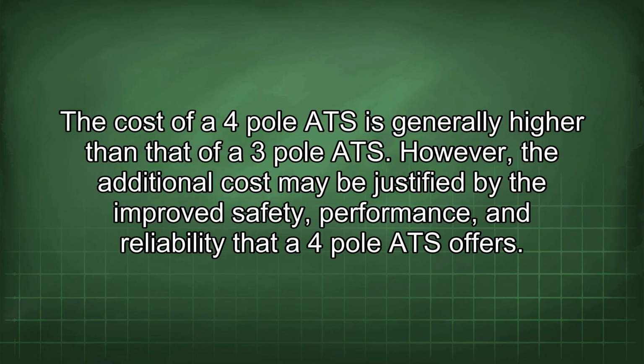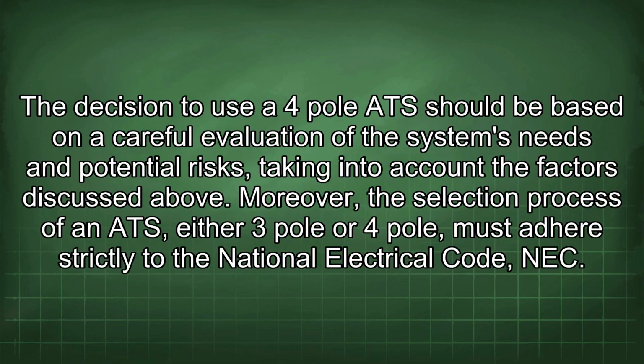The cost of a 4-pole ATS is generally higher than that of a 3-pole ATS. However, the additional cost may be justified by the improved safety, performance, and reliability that a 4-pole ATS offers. The decision to use a 4-pole ATS should be based on a careful evaluation of the system's needs and potential risks, taking into account the factors discussed above. Moreover, the selection process of an ATS, either 3-pole or 4-pole, must adhere strictly to the National Electrical Code (NEC).